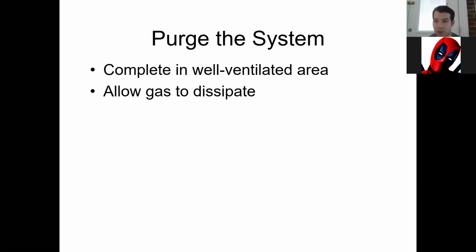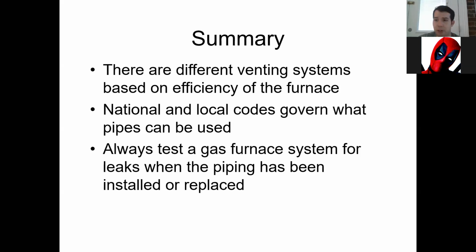But even then, there's going to be residual amounts of natural gas stuck in that line. So you will have to make sure you ventilate properly, because otherwise you're going to be working the whole time thinking, oh my gosh, I'm going to catch something on fire if I have a static shock spark or something. Because it's going to stink like rotten eggs. So that's one of the things you want to do if you're going to be taking apart any of the system's natural gas lines. Burn out the gas that's left in the line, and then ventilate anything that might be left in the line.